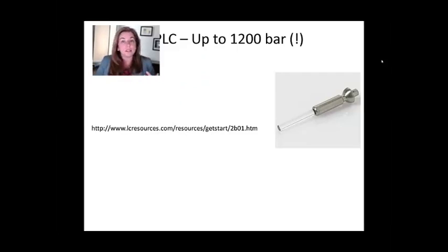And it's interesting how HPLC pumps work. First of all, they're all going to be stainless steel. Most plastic materials can't withstand those kinds of pressures without cracking or breaking. So one of the features of an LC system is a lot of expensive stainless steel machine parts that fit together to make sure that all of the liquid handling system is contiguous and you don't have any leaks. And the bane of your existence when you do liquid chromatography, believe me, is leaks. Because once some of that mobile phase starts coming out, your pressure isn't what you want it to be, you're leaking fluid, it's a mess, and you've got to go figure out where the leak is and fix it.